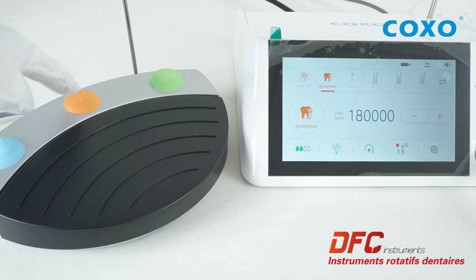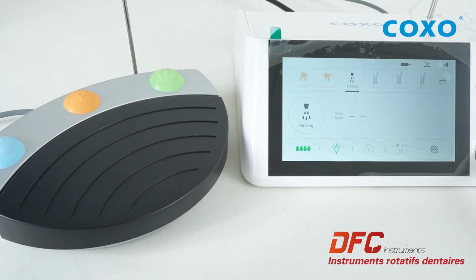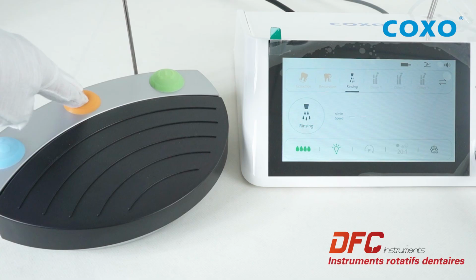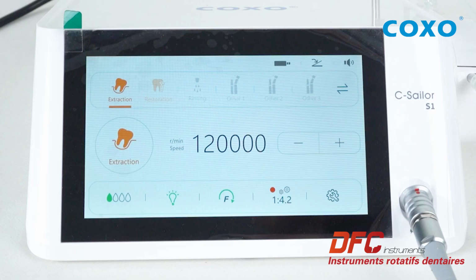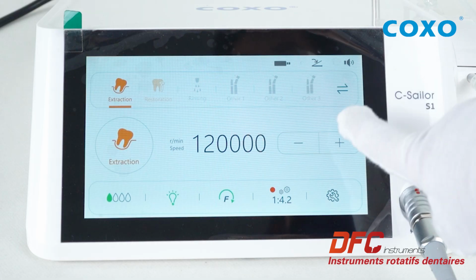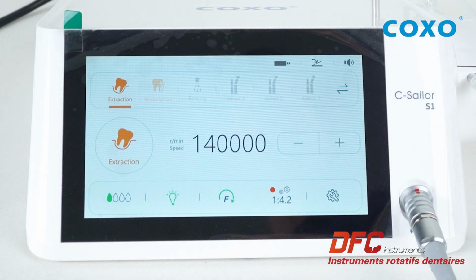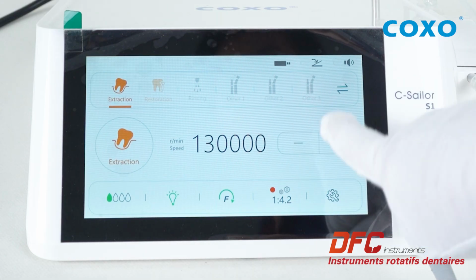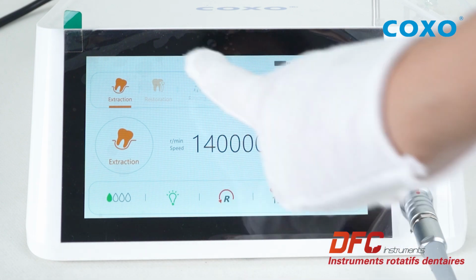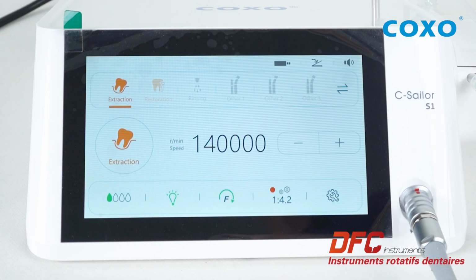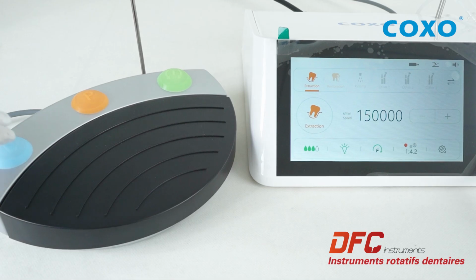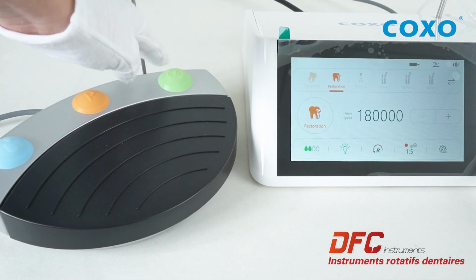It is also possible to change programs by pressing the orange P button on the pedal. Press this same P button for 2 seconds to return to the previous step. As in implant mode, the speed, gear ratio, and coolant are preset for all operations. You can adjust them using the plus or minus keys. Except for the motor direction, modified parameters will be saved automatically. As in implant mode, you can adjust the coolant level and forward or reverse gear using the buttons at the bottom of the screen, or directly on the pedal with the blue and green buttons.